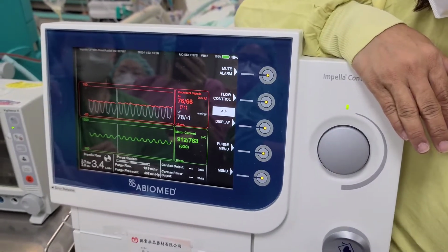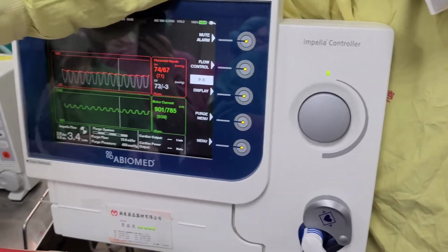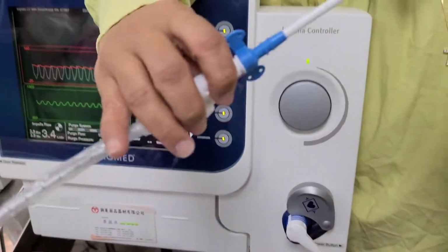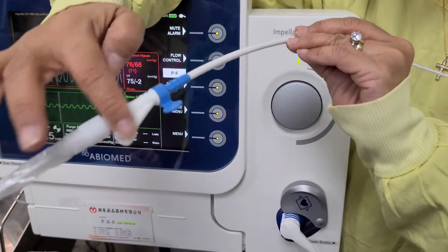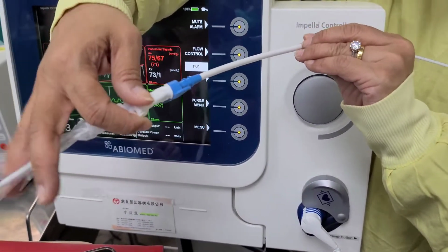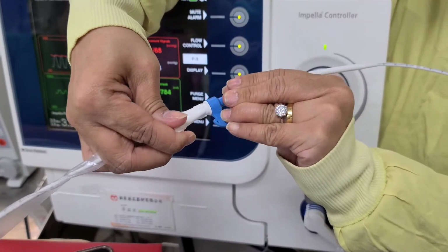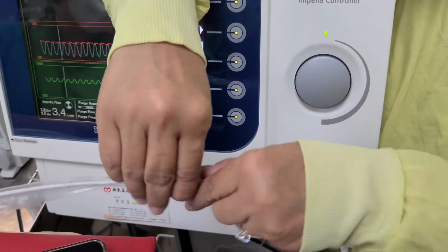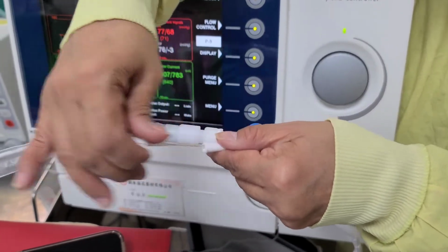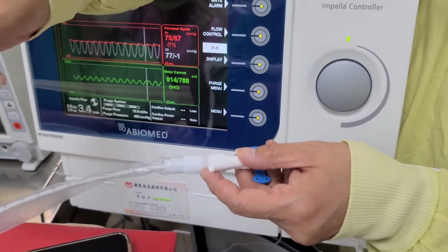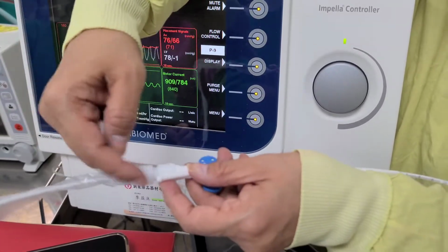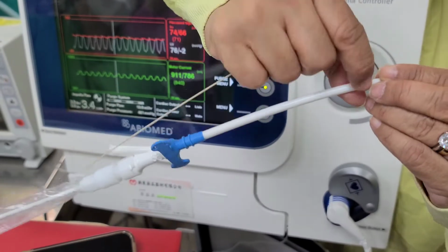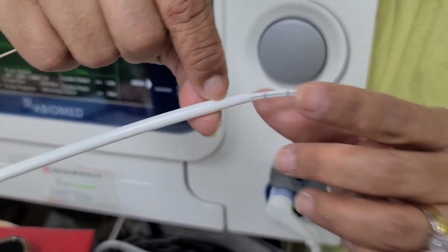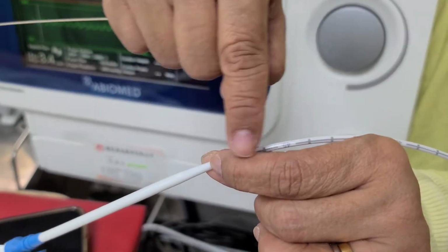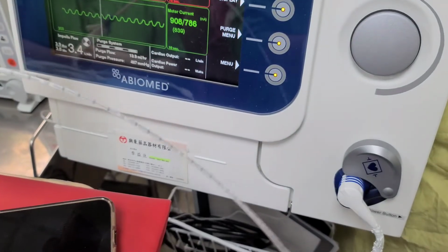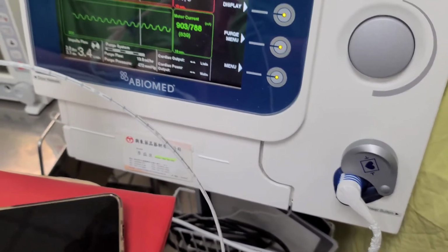So this is the introducer sheath, right? On the side of the introducer sheath is what we call a re-access port. This port allows the physician to insert a 035 guide wire. It will exit at the end of the sheath, at the sheath point, not outside the sheath, so it will be outside the catheter. So they can pull this whole thing out and leave the wire inside. Then they can pre-close if they want to.